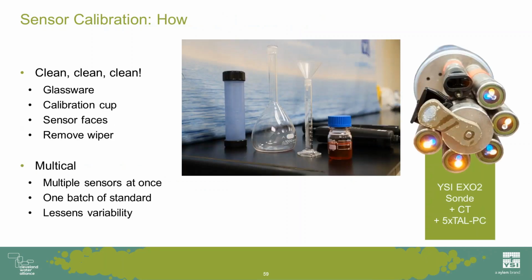Now, it may seem obvious when you're working with an optical sensor, but keep things clean. So keeping the face of those sensors clean, the calibration tools clean, that is really important at the point of calibration of any optical sensor, not just the algae sensors. If you are using the EXO platform, you really should take advantage of that multi-cal feature. And again, though, with optical sensors, cleanliness really is next to godliness.